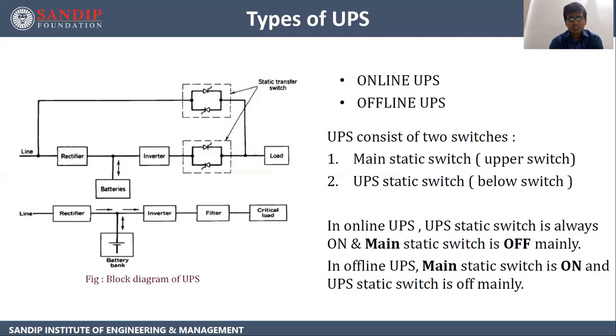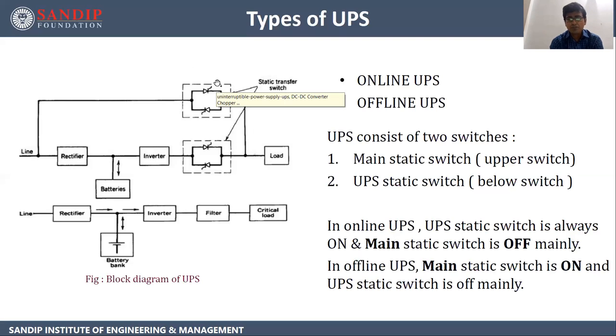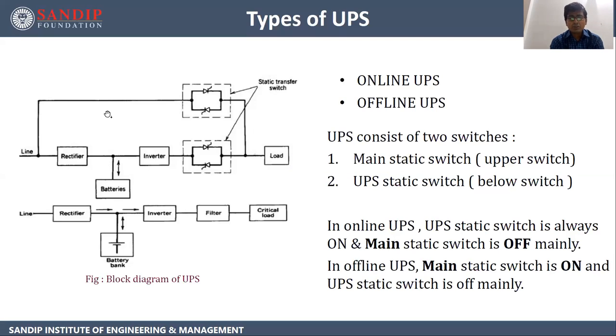Now, how to remember the difference between online and offline UPS through this figure. When we talk about online UPS, power conversion takes place through the UPS path and is fed to the load — so the UPS static switch is mainly on, whereas the main static switch is off. In offline UPS, power is not going through the UPS mainly — most of the time it goes off the UPS, meaning directly the line is fed to the load. That is only possible when the main static switch is on and the UPS static switch is off.